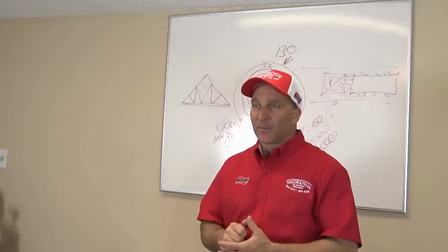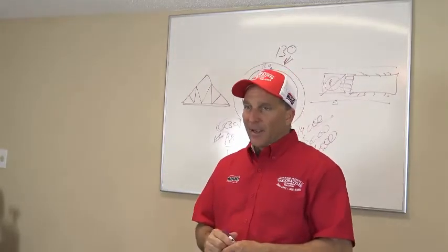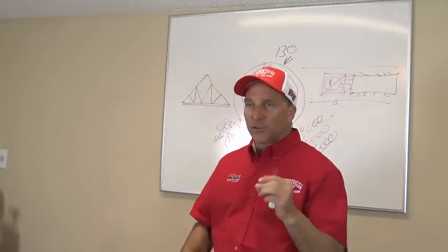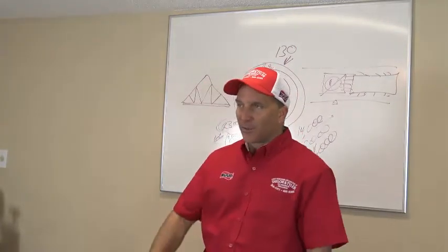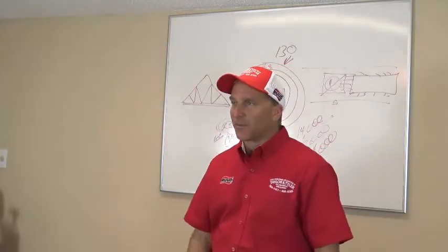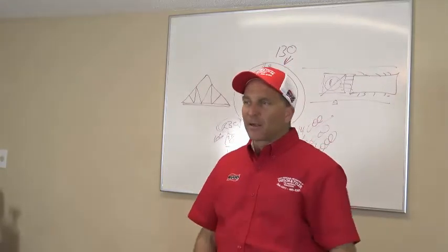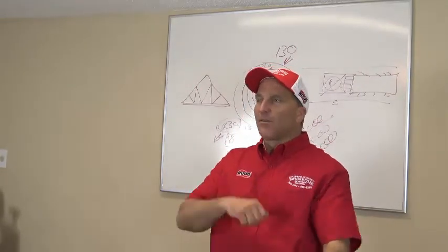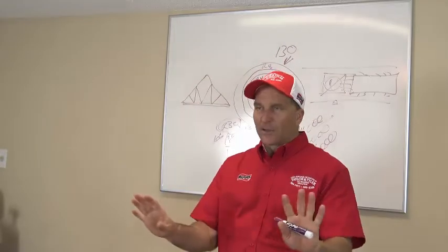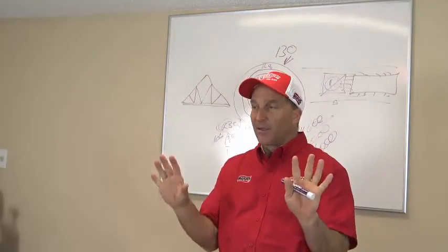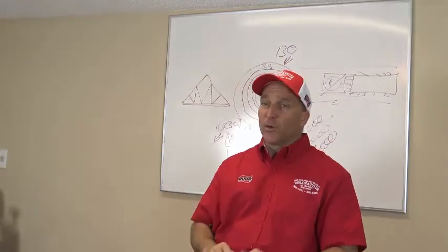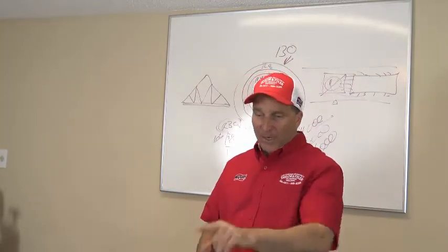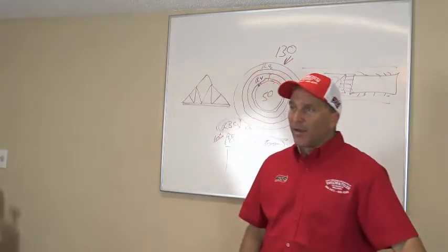I said, okay. So I went over there, and boom, as soon as you put the fuse in, it shorts the breaker, right? Trips the breaker. I said, okay, now watch. I'm disconnecting the compressor. So I pulled the leads off of the compressor, put them all out to where they can't touch anything. And I said, now look, when I put this fuse back in, that compressor doesn't have any voltage to it, right?